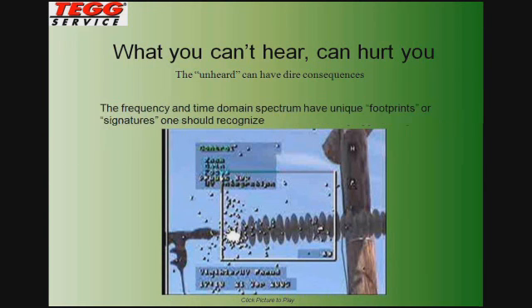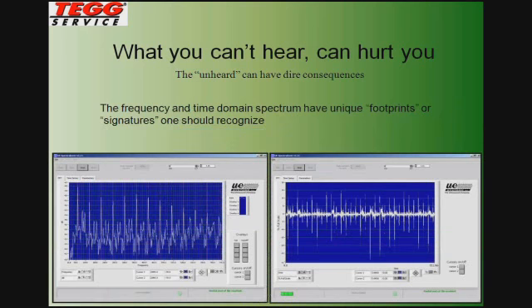It makes it easy for us, when we're looking at it, if you know what you're looking for, to pick this out for nuisance or destructive corona, in that there's a lot of symmetry. So on the frequency domain, unlike the arcing and tracking where we only had the first couple of harmonic frequency faults, we see that each 50 or 60 hertz frequency has a peak or a fault all the way across the spectrum, and it is loaded or very rich with frequency noise in between each one of those peaks. That's the first indicator that we're dealing with corona.